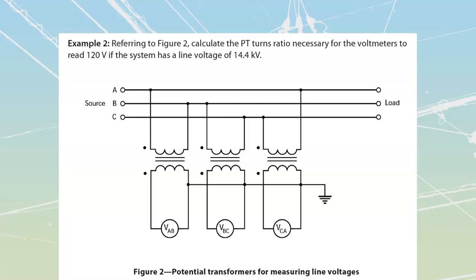Example number 2. Calculate the PT turns necessary for the voltmeters to read 120 volts if the system has a line voltage of 14.4 kV. Well, if we take a look at what I have connected on the primary side, I see that my primary is going across from line to line over here. So since I'm going across from line to line, if this is going to be a line voltage of 14.4, I'm going to put the whole 14.4 kV over top of that winding.